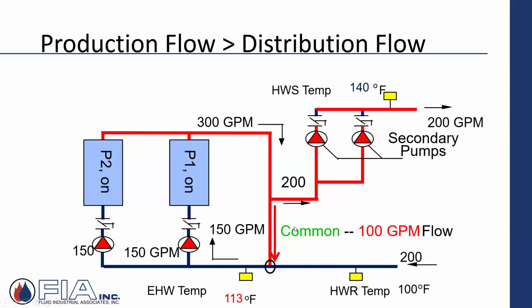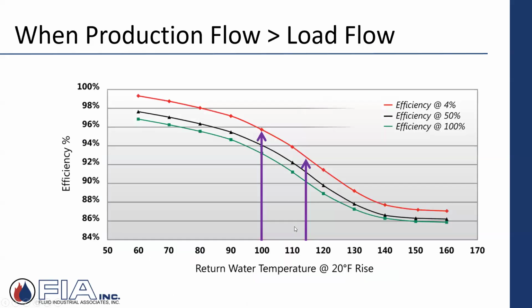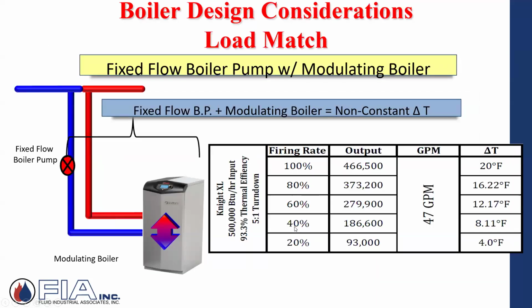If I do fixed speed and the load out here says, hey, I only need X, some of that hot boiler water goes right back to the return. What does it do to the return temperature? Elevates it. And as it elevates it, look what it does to the efficiency of that boiler plant. It can start to reduce. So the building owner, the guy paying the bill, starts to lose some of the potential energy savings.